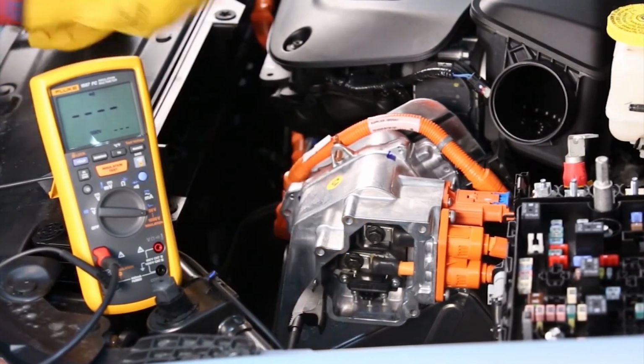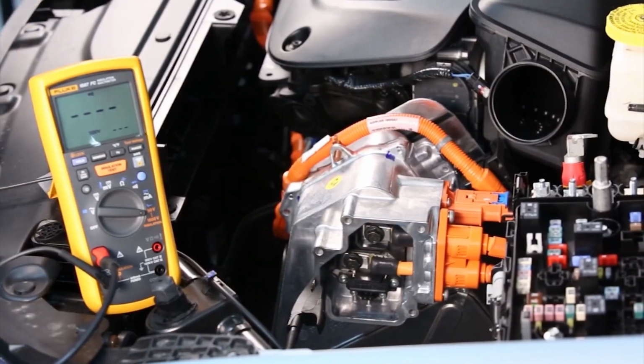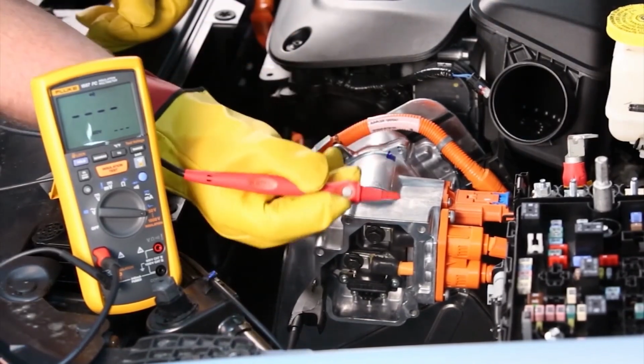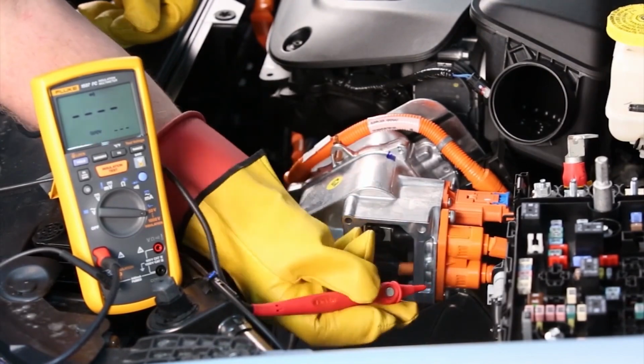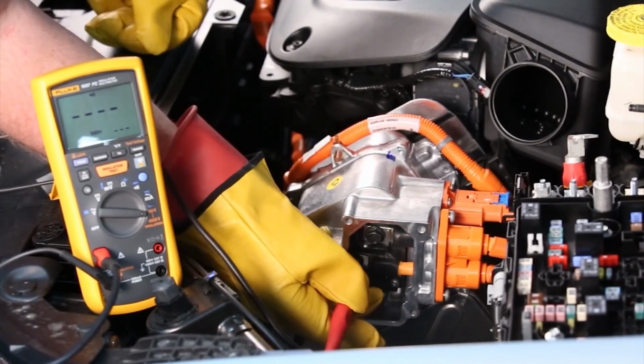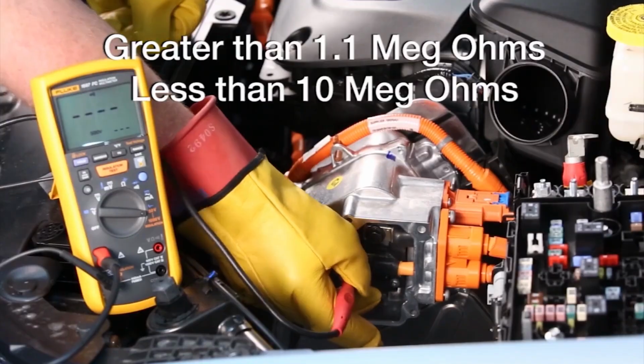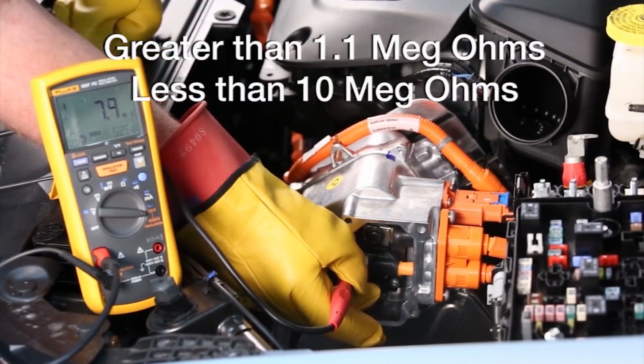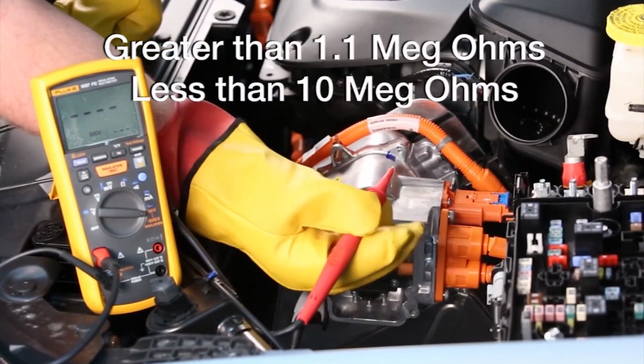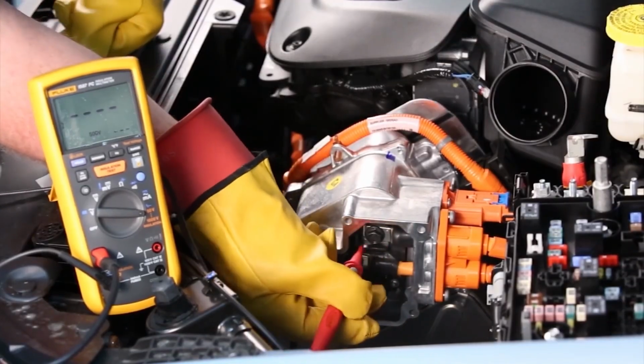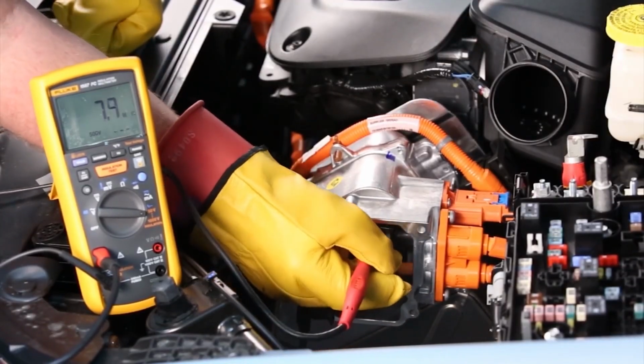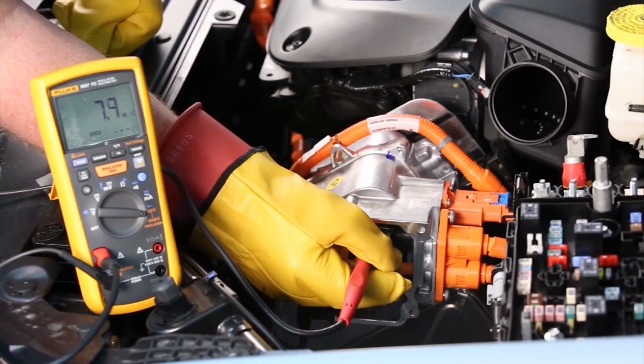First, measure between the positive high voltage terminal and chassis ground. Secondly, measure between the negative high voltage terminal and chassis ground. The measured isolation resistance should be greater than 1.1 megohms and less than 10 megohms. Compare these measured values with those taken during the high voltage power-up to verify the integrity of the repair. Refer to the service information for further details on this procedure.